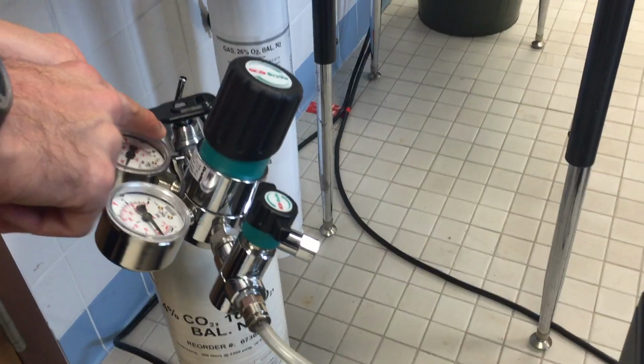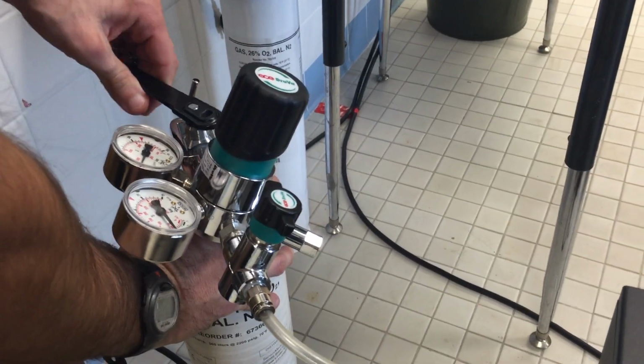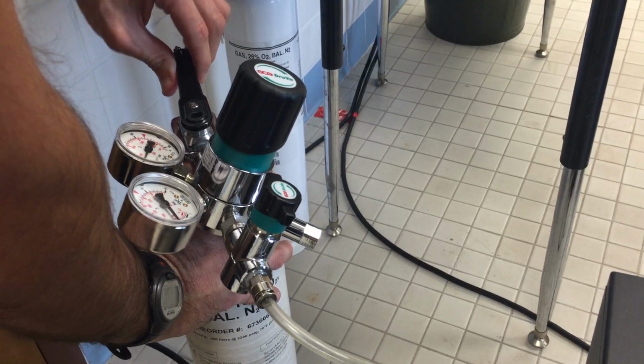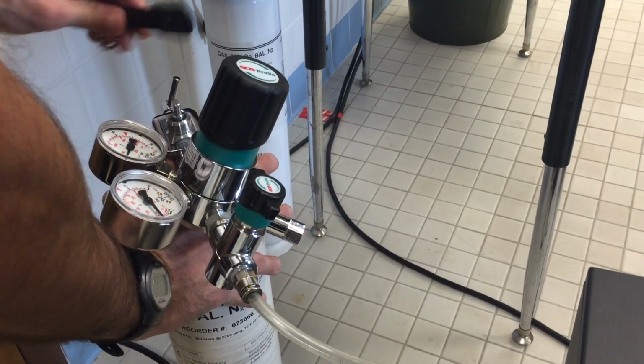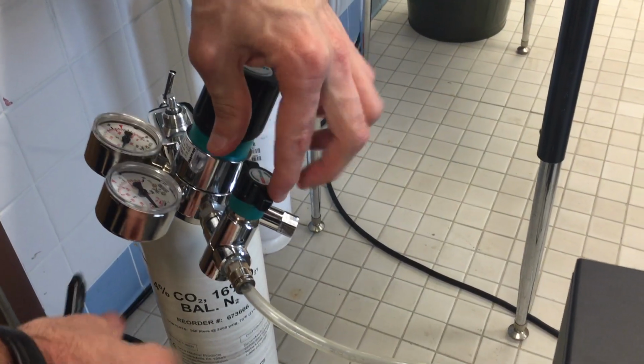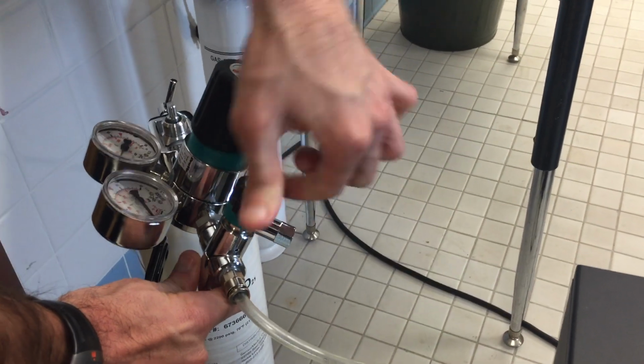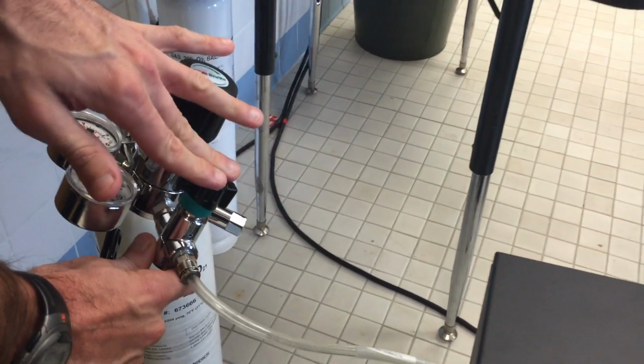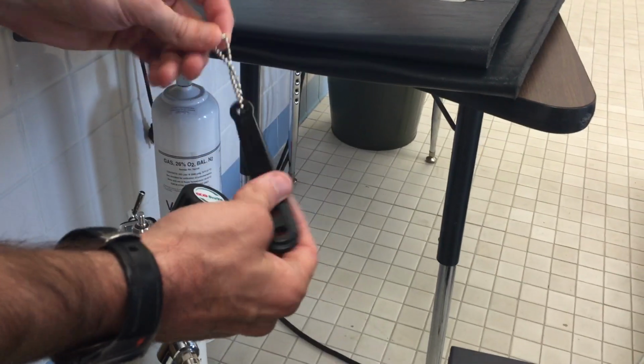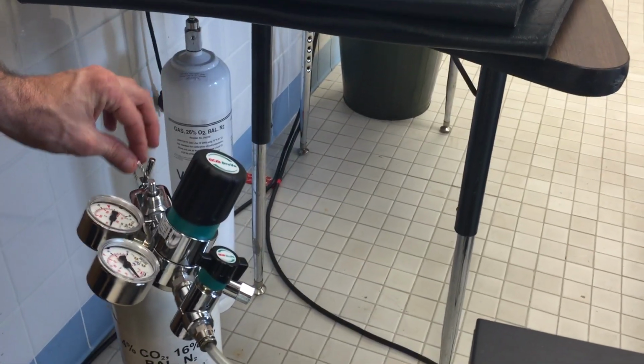However, the last step that has to be done is we have to turn off the gas we turned on in the beginning. So we go back to our tank, we get our tool. First thing we do again, we turn off our little silver knob. Now we're turning clockwise about a quarter turn, and you'll see it'll get snug on its own. You don't have to really wrench it, just get it tight enough. Same thing here, we turn it clockwise. We just want it to be tight, not super snug. We put our tool again back right where it needs to be, and we are done with the calibration process.